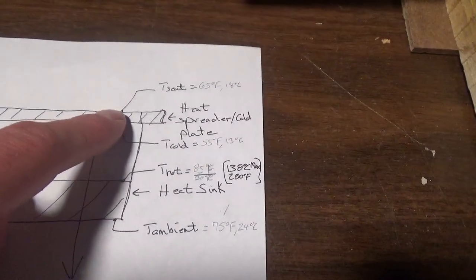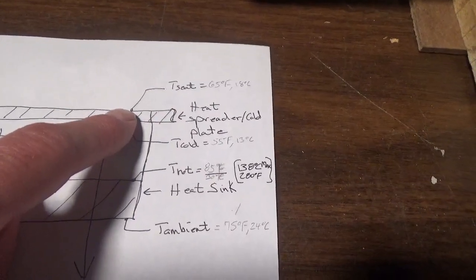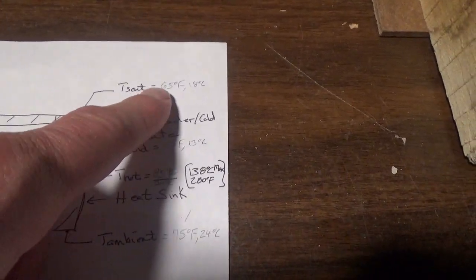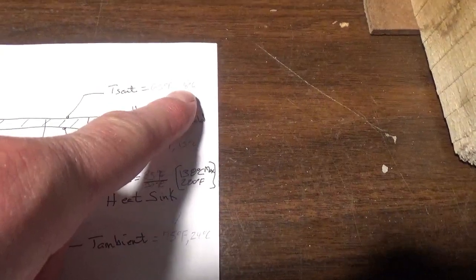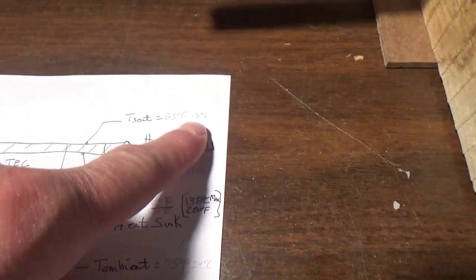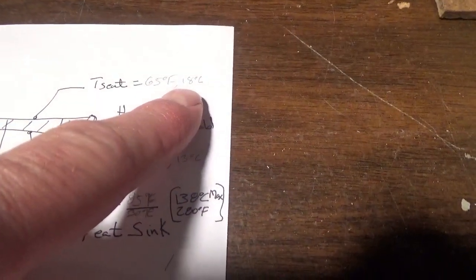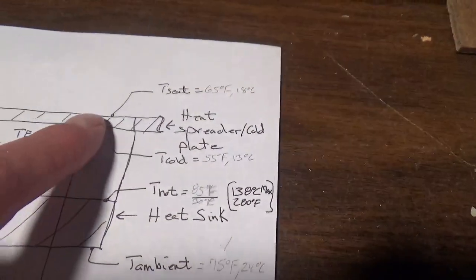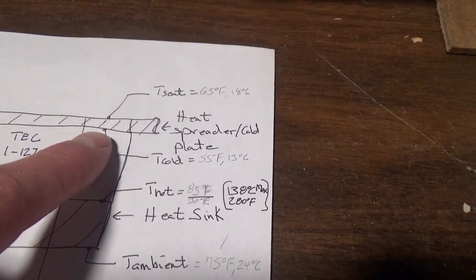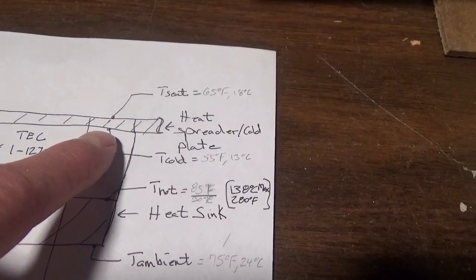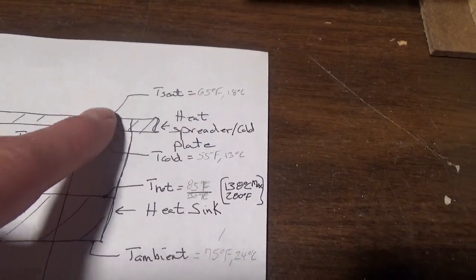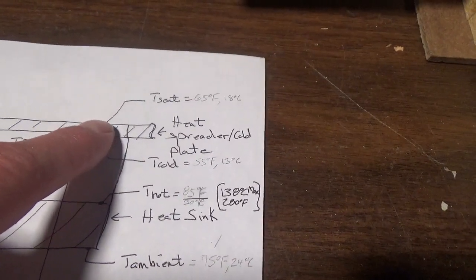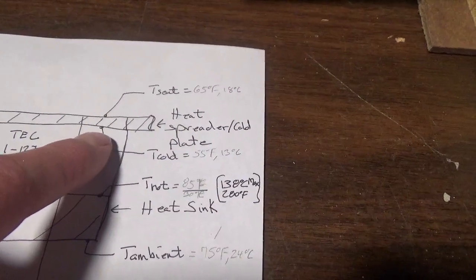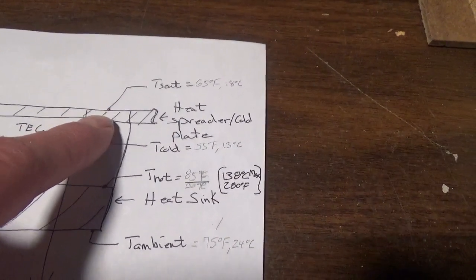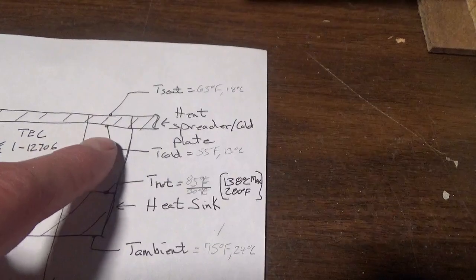Up here we said the top of the cold plate where you're going to sit, maybe let's call it 65 degrees Fahrenheit, which is 18 degrees Celsius. You can see that in there. There's probably going to be like a 10 degree Fahrenheit difference from what the cold plate will have to be in order to get this to 65. This is probably going to have to be 55, because there's going to be some thermal resistance through here.